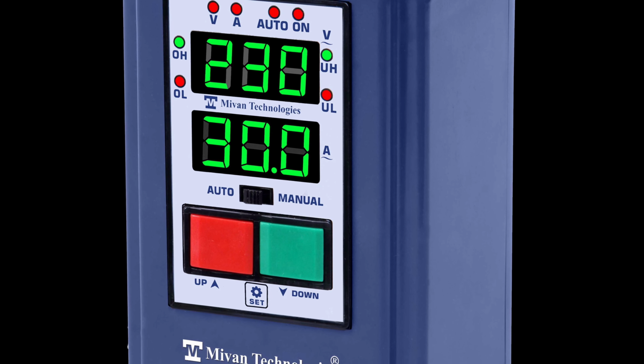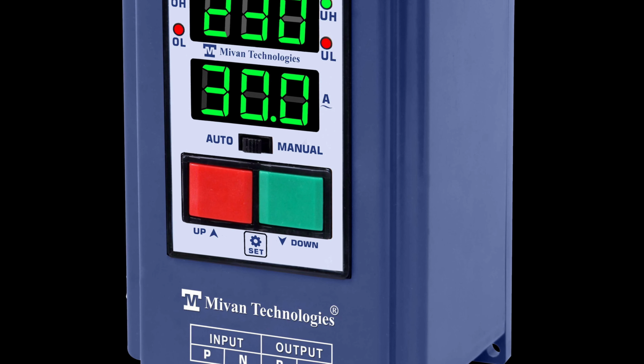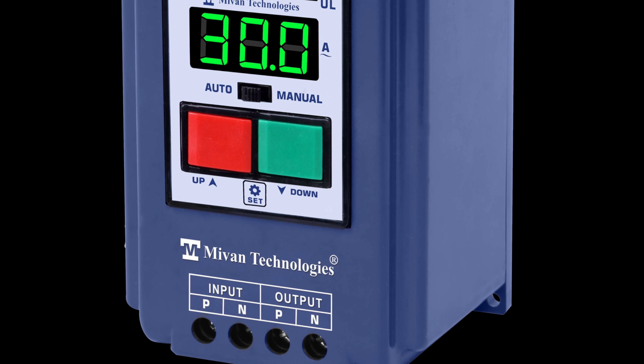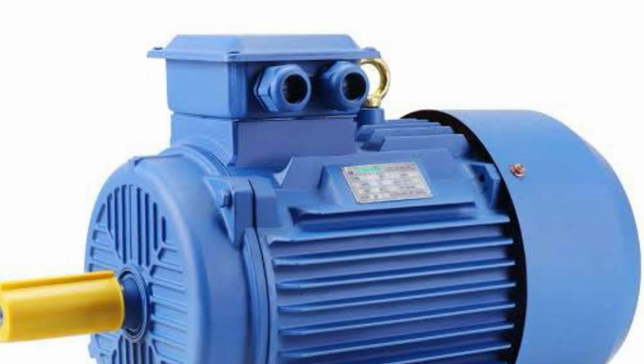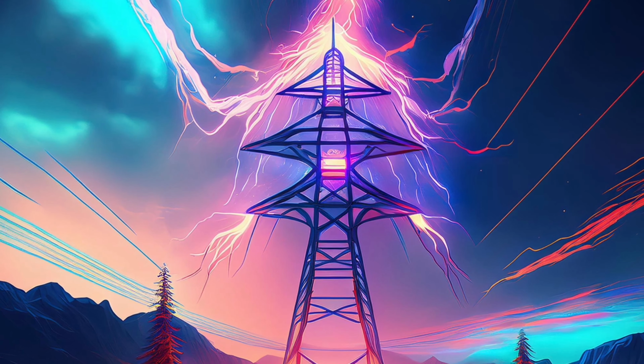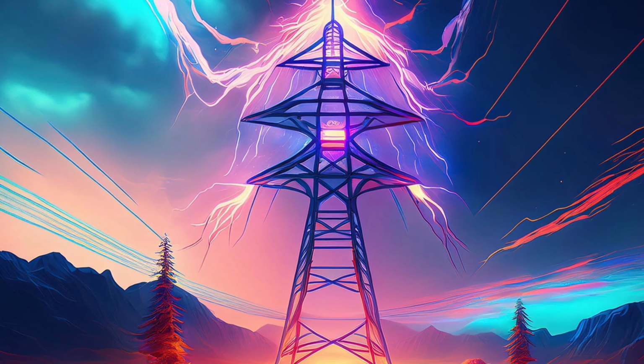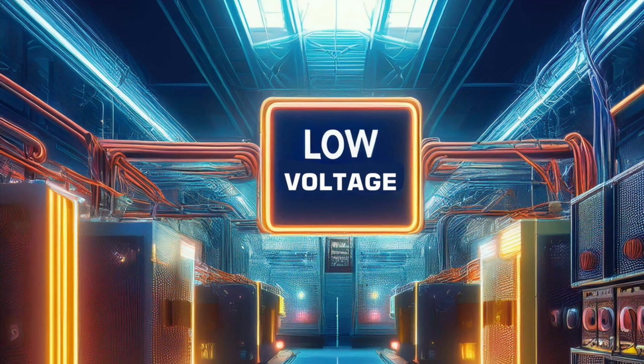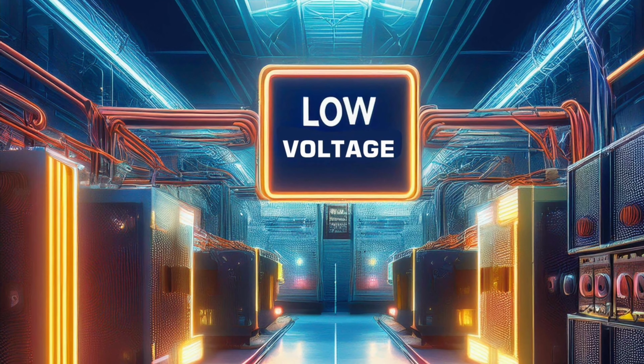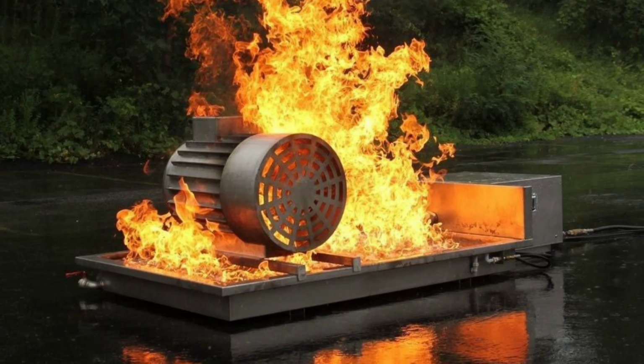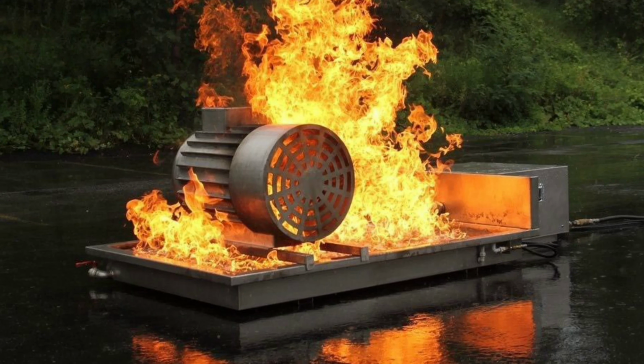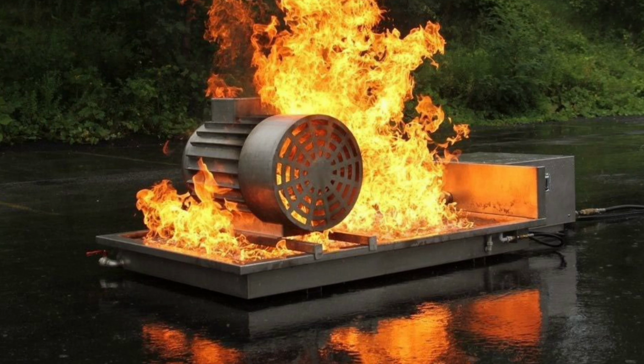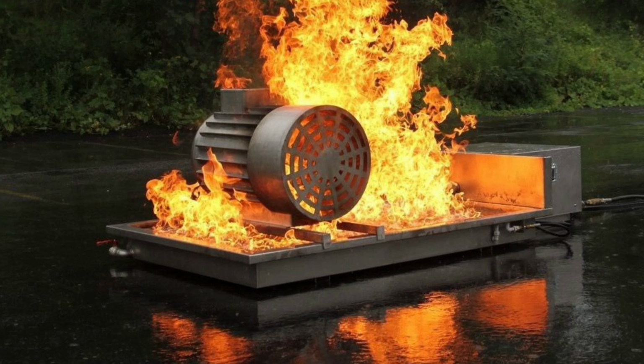This is the Mivan Technologies heavy duty digital single phase water level controller that is suitable up to 3 HP motor. This device provides high voltage and low voltage protection. It saves the motor from high and low voltage fluctuations. It also provides electronic overload protection and protects the motor from burning due to overload.